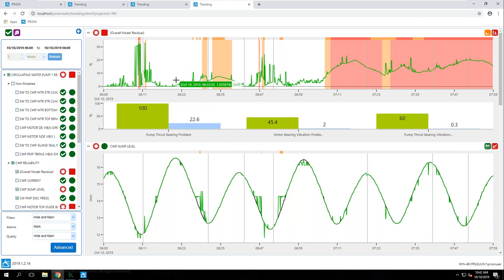What Prism will do is, as that model residual starts to grow, it will pattern match against those known failure modes and tell you which failure mode is most likely occurring. So we can see here on my screen, we have a pump thrust bearing problem.